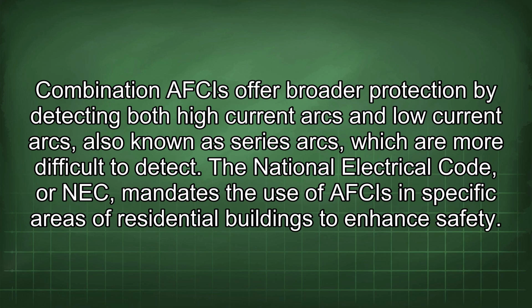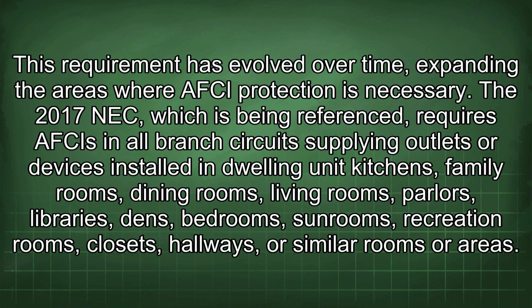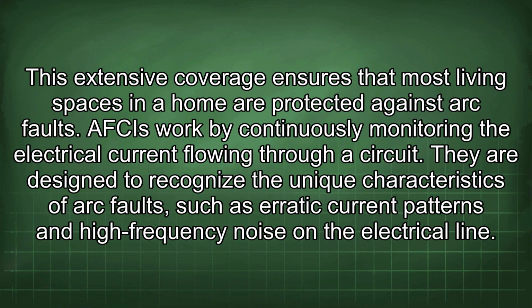The National Electrical Code, or NEC, mandates the use of AFCIs in specific areas of residential buildings to enhance safety. This requirement has evolved over time, expanding the areas where AFCI protection is necessary. The 2017 NEC, which is being referenced, requires AFCIs in all branch circuits supplying outlets or devices installed in dwelling unit kitchens, family rooms, dining rooms, living rooms, parlors, libraries, dens, bedrooms, sunrooms, recreation rooms, closets, hallways, or similar rooms or areas. This extensive coverage ensures that most living spaces in a home are protected against arc faults.